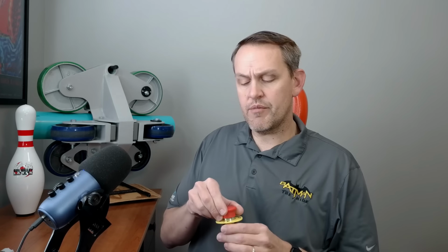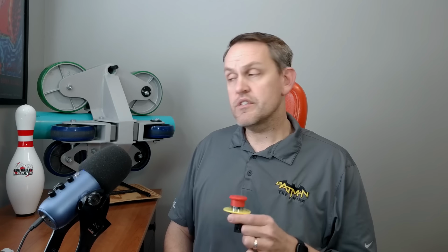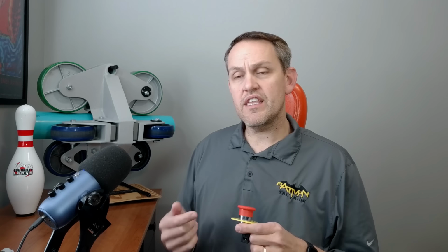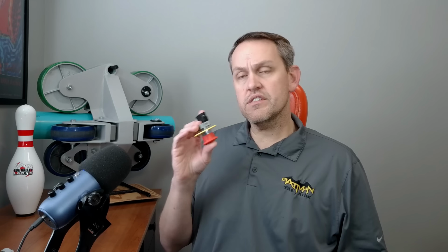So the ESR, emergency stop relay, is typically monitored at the panel. So you might look in there and say, oh, is my ESR on or off? Which means, is my emergency stop relay on or off? This would be used to say, like, you come in and the e-stop button is up. Well, did anyone push the e-stop? No, but the ESR relay is dropped out. The ESR, the emergency stop, is not the only thing that will drop that out. Drives and other systems can also drop that relay out too when they register a problem with their circuitry as well.